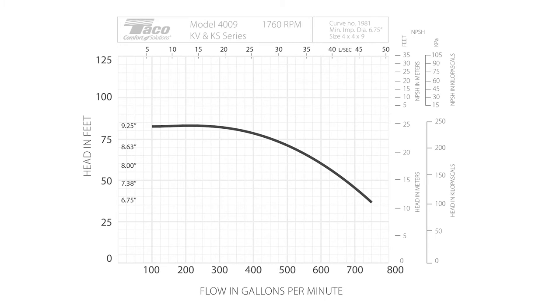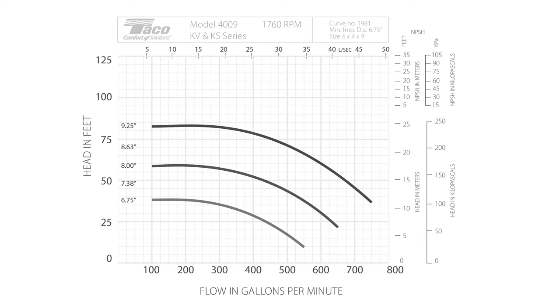This is the curve for this particular pump with the largest impeller diameter — in this case, it's 9.25 inches. We do the same thing with the data points for an 8 inch diameter impeller and a 6.75 inch impeller.